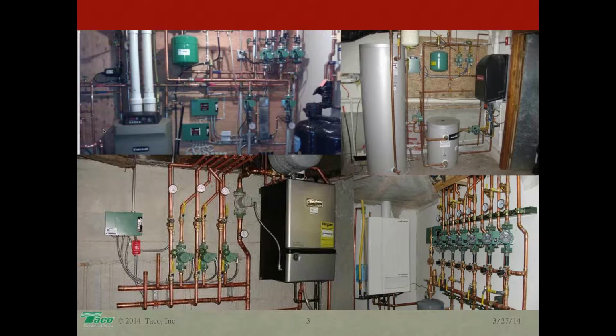Now, some of these boilers are changing. Some of them are evolving. The manufacturers are making heat exchangers that have lower and lower pressure drops. And if you look into any of the installation manuals of the boilers you are installing, you will find that they all provide you with options for boiler piping installation. You can pipe them up in a traditional in and out direct piping method, although they prefer and recommend a different type of piping strategy, which we will discuss.